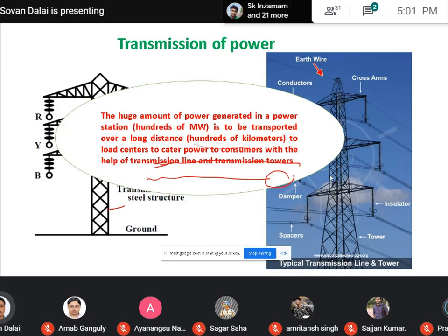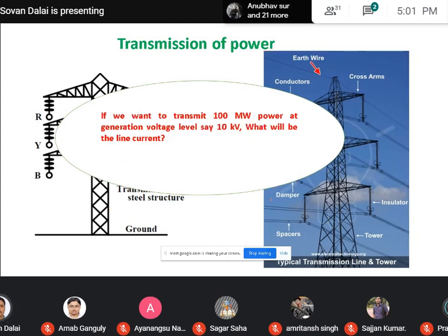So suppose power is generated in Kolaghat, and that power is transmitted to Kolkata, and the distance between them is nearly 70 kilometers. So we generate power at certain places and deliver that power over a distance. In order to deliver that power from the generator side to the load side, if we lose more power, that will not be economical. So to increase the efficiency of power transmission, the power is generally transmitted at very high voltage. So what is the advantage of transmitting power at high voltage?